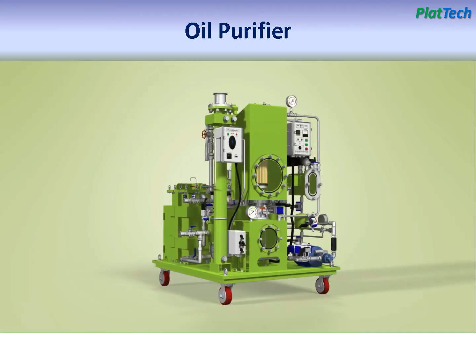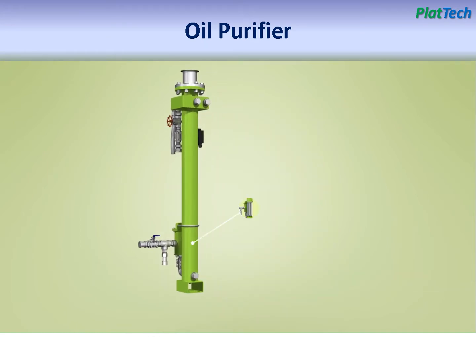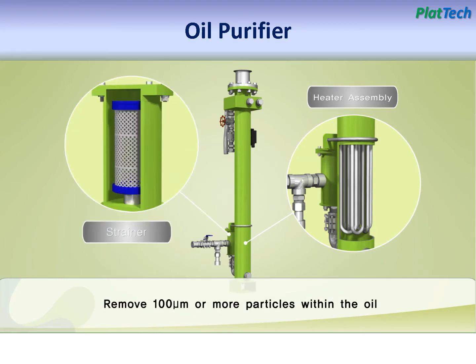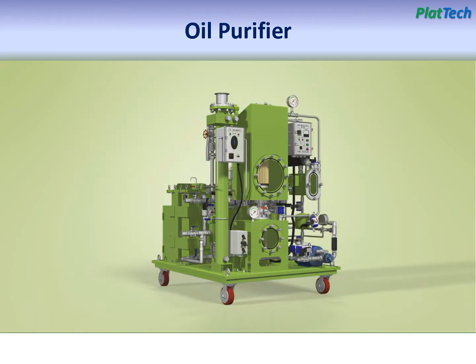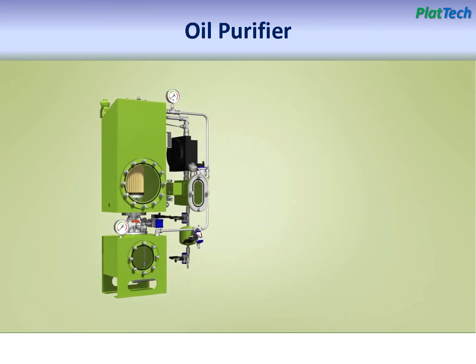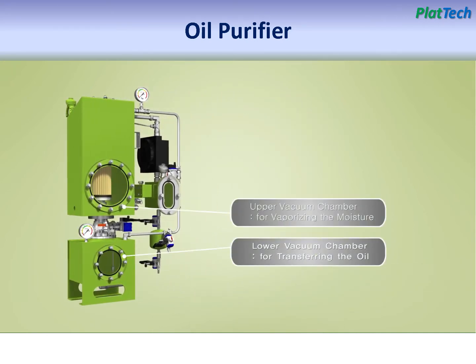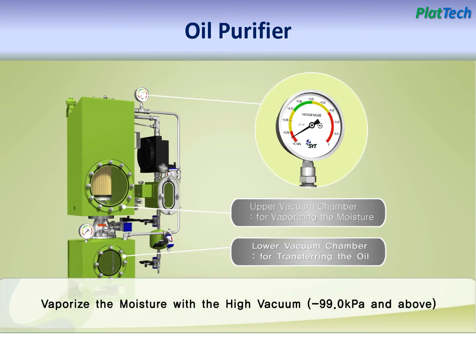Electric heater will keep the oil feed temperature at 60 to 65 degrees Celsius. Suction strainer will remove particles greater than 100 micrometer. Pure vacuum system for water removal is equipped with upper and lower vacuum chambers. Upper vacuum chamber is used for vaporizing the moisture, and lower vacuum chamber is for transferring the oil. One of our unique technologies keeps high vacuum at around minus 99 kilopascal or above continuously, so moisture removal efficiency can be maintained in good condition all the time.